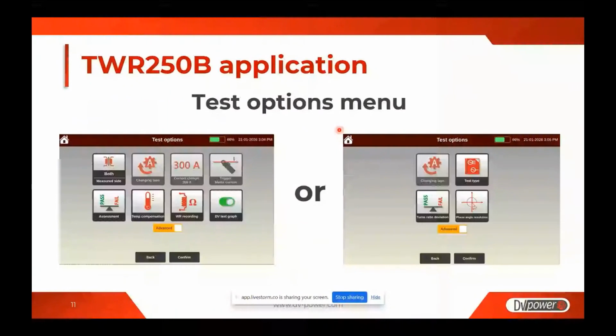So the right-hand side is related to turn ratio measurement, and then you can select whether you would do both simultaneous and sequential test, or we will perform only simultaneous measurement. And with turn ratio deviation pass-fail criteria, you can select the mentioned pass-fail criteria, whether it is 0.5% as per standard, or if you want to select something else, but 0.5% is the default.